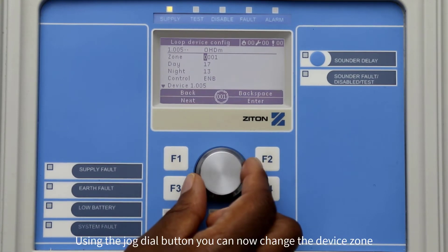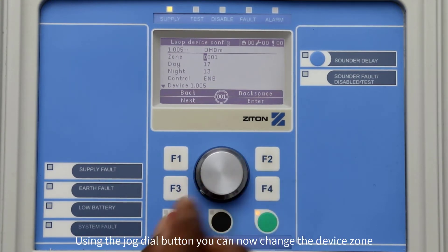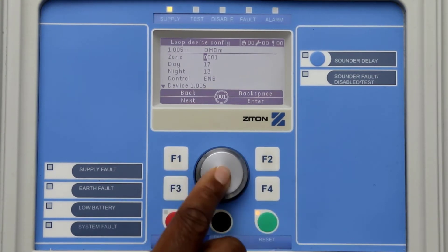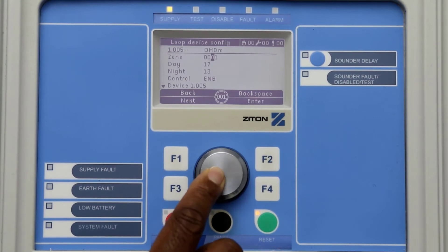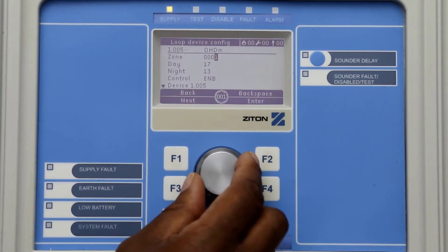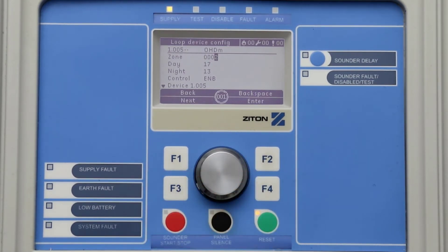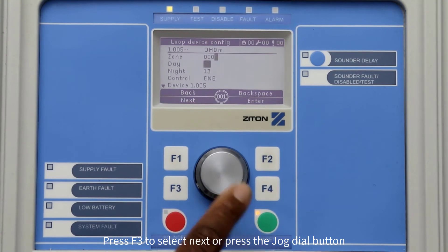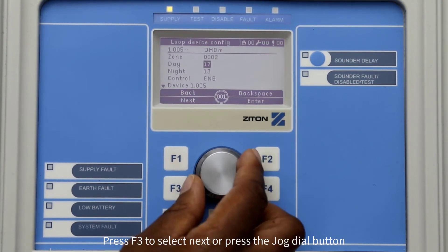You can now change the detector zone by simply using the jog dial button. Pressing the button will move the cursor one step over to the right. For this example, I will change my multi-sensor from zone number one to zone number two. Once you have finished changing the zone, press F3 to select Next or press the jog dial button to move the cursor to the daytime profile setting.